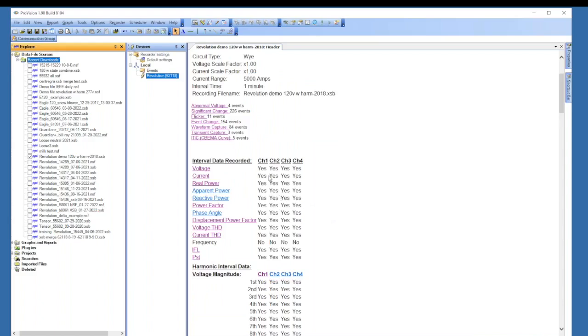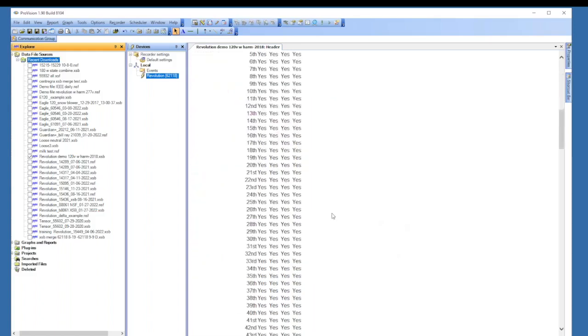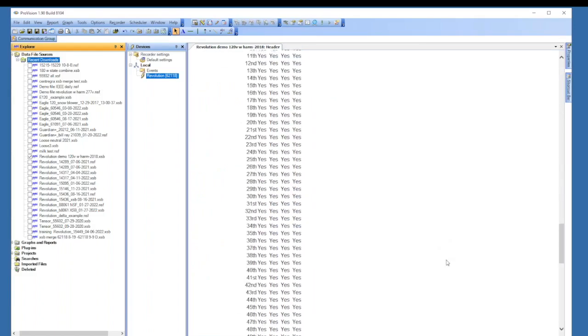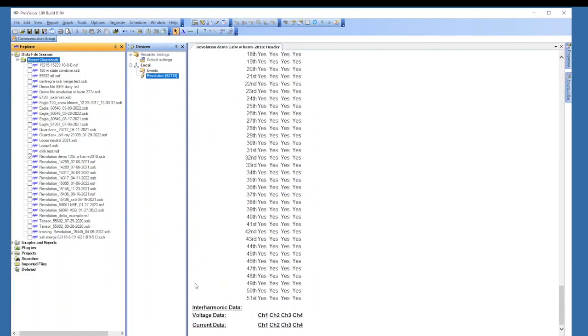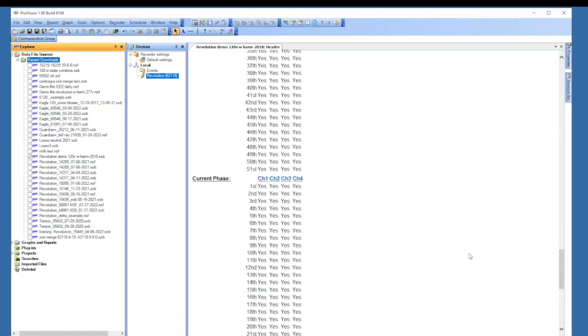And under interval data, if we only chose 3 channels, then channel 4 would have no's in it. You can see this one, frequency was not recorded. We do record frequency only on channel 1. And then if you recorded harmonics, you'll see which harmonics were recorded. And for the Revolution, if you recorded interharmonics, those will be down there also.